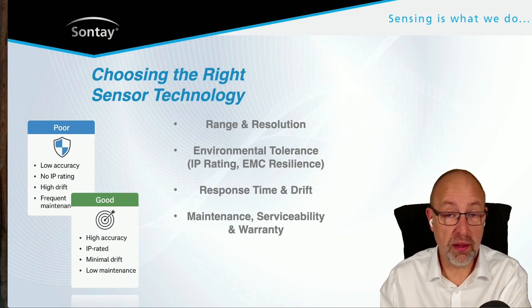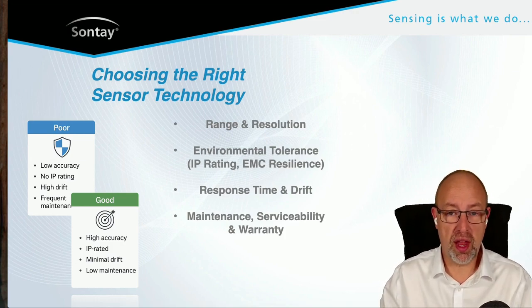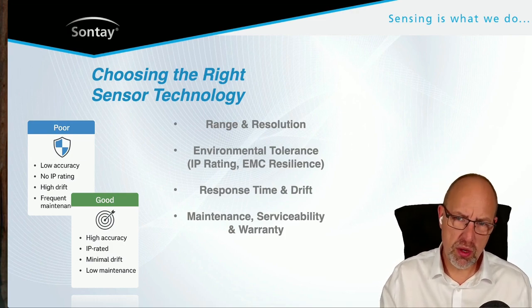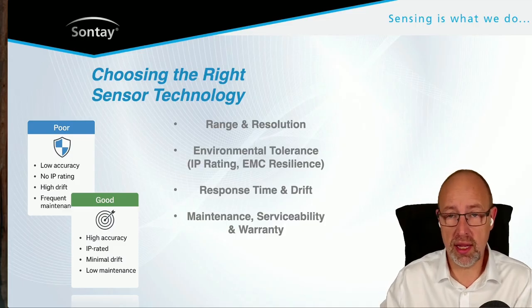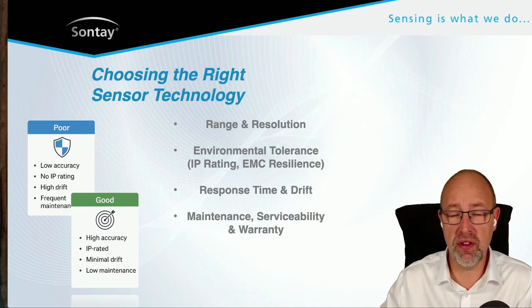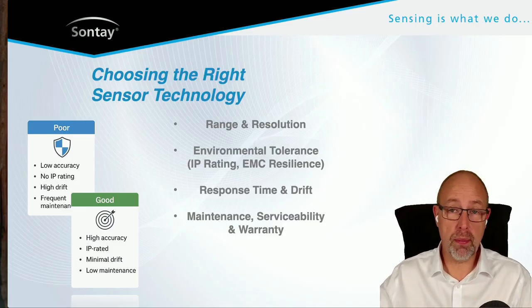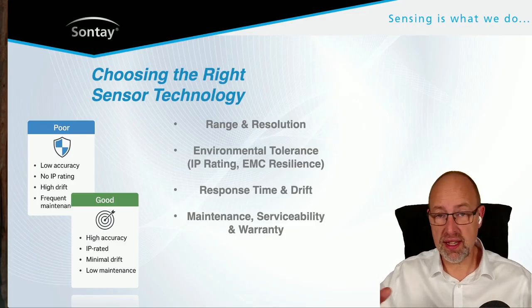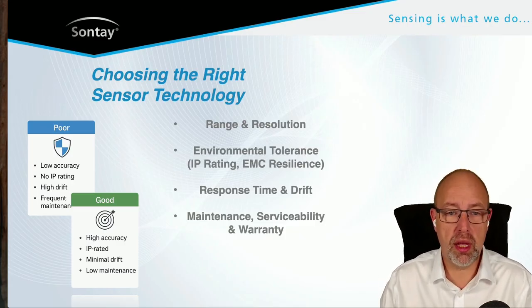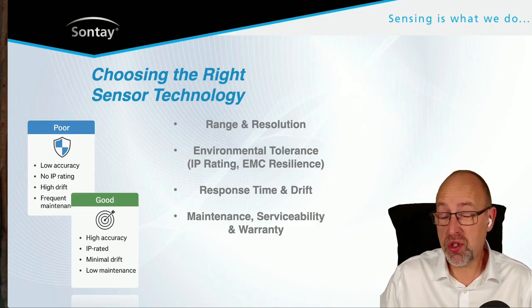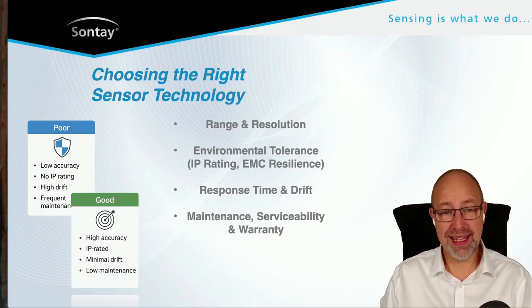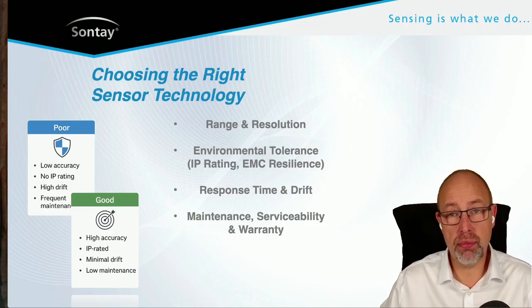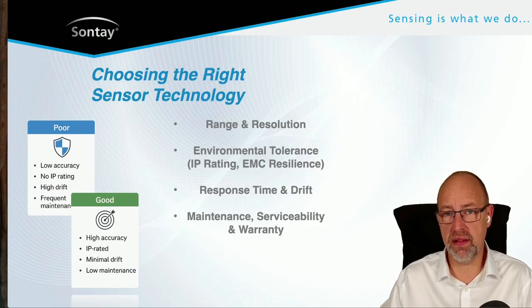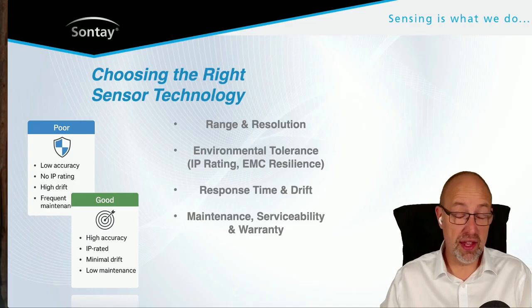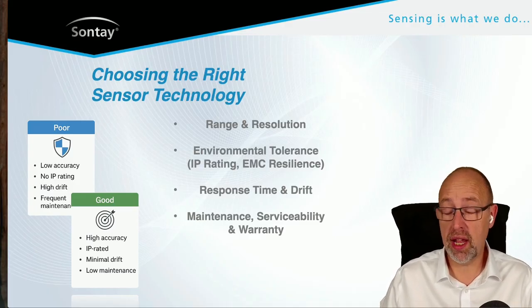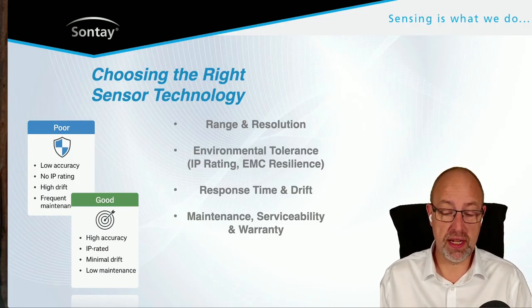It might work fine, but there is more potential there if it's next to that equipment. So we do have to think about the resilience to EMC, electromagnetic interference, and we also have to think about spacing those sensors out to make sure that doesn't become an issue. Response time is very important in data centers, particularly temperature sensors. Different temperature sensors have different response times. It's often misconstrued as an accuracy level for a sensor.